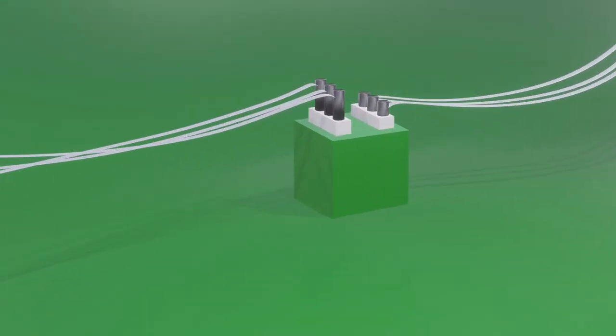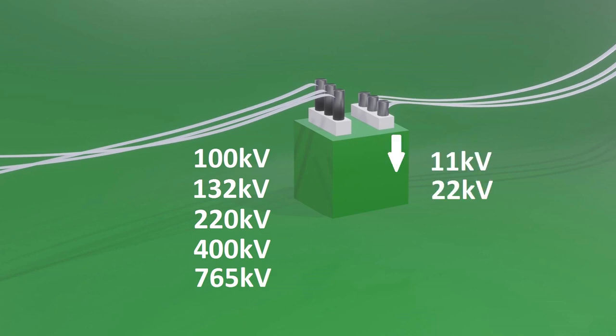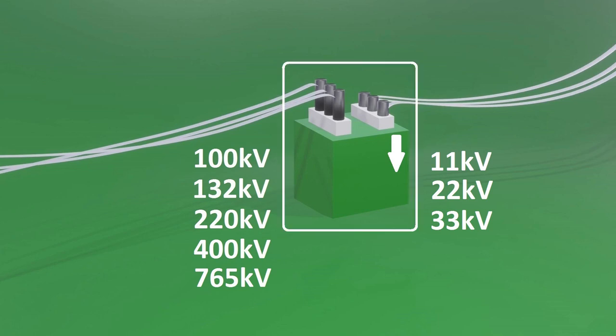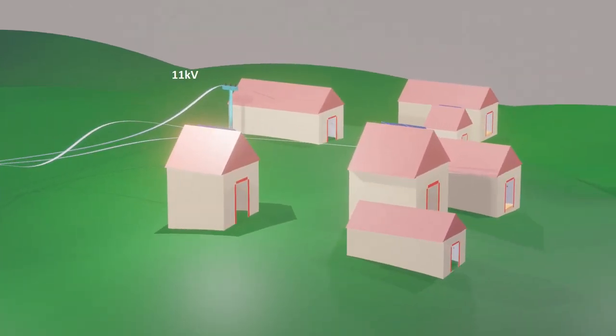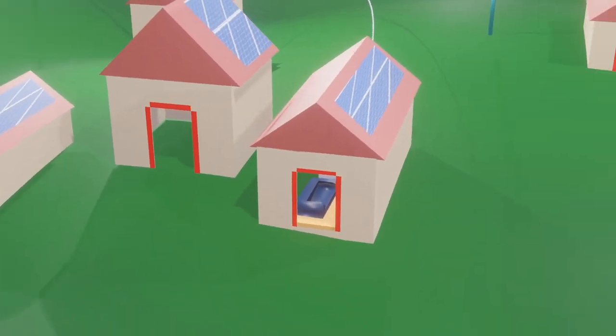At consumer regions, this extra high voltage — 100 kV, 132 kV, 220 kV, 400 kV, and 765 kV — is stepped down to 11 kV, 22 kV, and 33 kV using power transformers at substations. This stepped-down power is brought near the consumer areas. At the consumer end, this 11 kV, 22 kV, and 33 kV level is again stepped down to 440 volts using distribution transformers. Finally, this 440 volts 3-phase power is distributed to homes in a single-phase format, of which the voltage is 230 volts. This 230 volts of power is used in our homes.